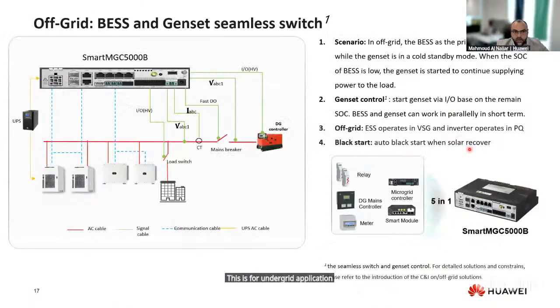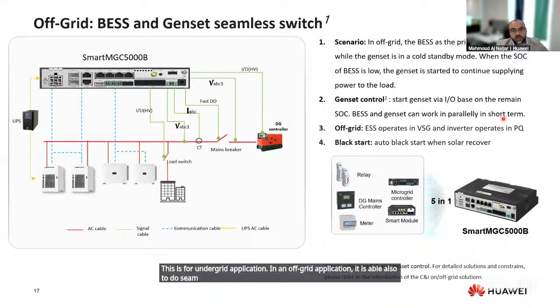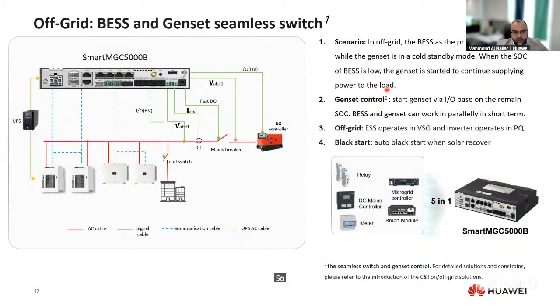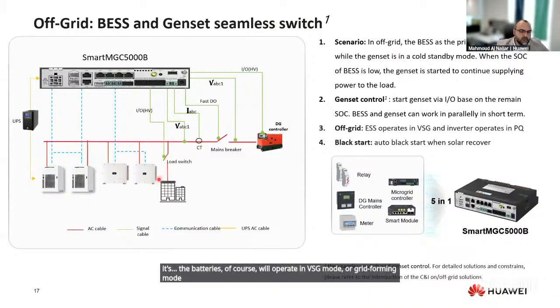And in an off-grid application, it is also able to do seamless switching from PV-ESS to DG. So all the controlling can be done through our smart MGC controller. The batteries, of course, will operate in VSG mode or grid forming mode, and the inverters will work in PQ mode or grid following mode. And everything is managed and controlled through the smart MGC.